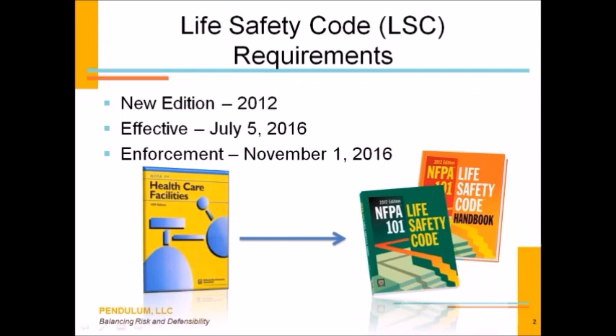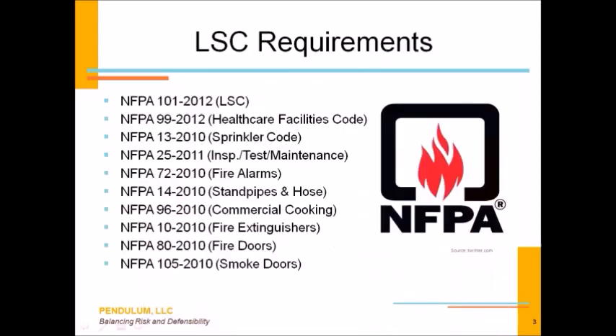of the code. When it comes to CMS compliance and regulated healthcare facilities, we know that you are dealing with the 2012 edition of NFPA 101, the Life Safety Code, and the 2012 edition of NFPA 99, the Healthcare Facilities Code. Enforcement of these editions started in November of 2016 with an effective date of July 5th of 2016. The previous edition of those codes was the 2000 edition of the Life Safety Code and the 1999 edition of NFPA 99, as enforced by CMS. So we're only focused on the CMS regulations right now.